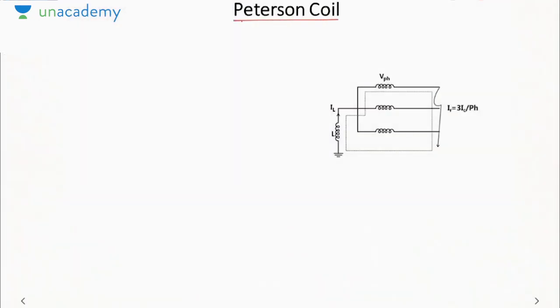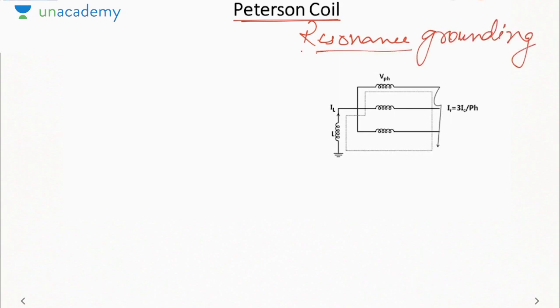The next method is called as Peterson coil, or the case of resonance grounding. Resonance means whenever the inductance cancels the effect of capacitance completely, system is said to be under resonance. So here also we are using reactance grounding, but the reactance is chosen such that it cancels the effect of capacitance or the line charging current. We just now saw whenever there is a line to ground fault, whatever the current is flowing in this wire, it is equal to 3 times I charging.